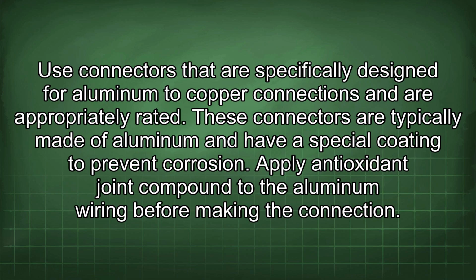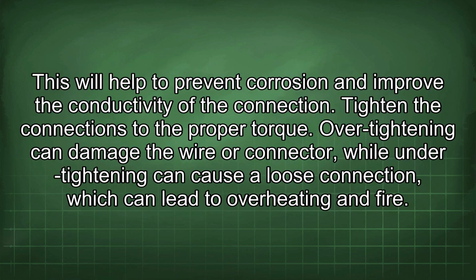Use connectors that are specifically designed for aluminum to copper connections and are appropriately rated. These connectors are typically made of aluminum and have a special coating to prevent corrosion. Apply antioxidant joint compound to the aluminum wiring before making the connection. This will help to prevent corrosion and improve the conductivity of the connection. Tighten the connections to the proper torque.